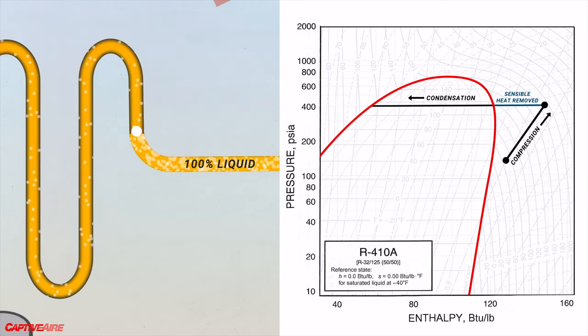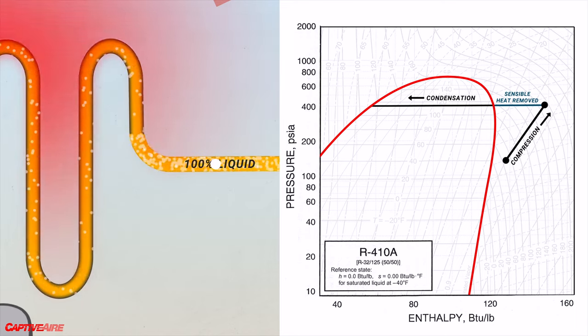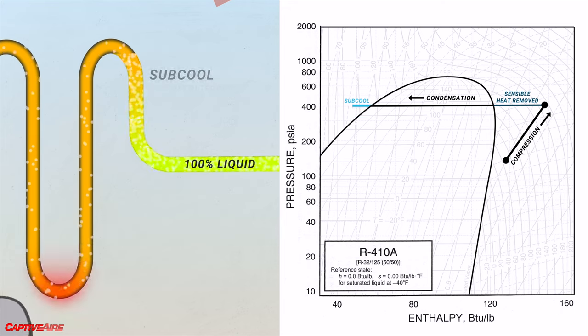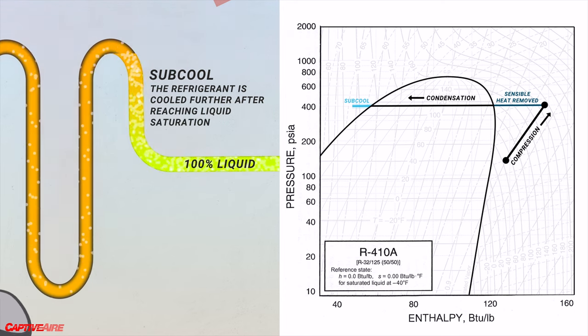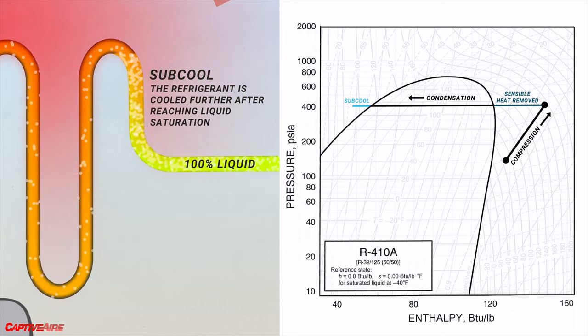In an ideal, perfect world we would stop right as the refrigerant has just fully condensed to liquid. But in real life, we have to cool the liquid down a little bit further — this process, which happens towards the exit of the condenser, is called subcool. In the condensing coil there's a saturation temperature, and we like to cool the refrigerant just below that saturation temperature by about 10 to 20 degrees. In a perfect world we'd shoot for zero degrees of subcool for maximum energy efficiency, but due to changing dynamics of airflow and indoor and outdoor temperatures, we have to build in some tolerance into the refrigeration cycle so we don't condense too early or too late in the coil. So we build in a little buffer — that's called subcool.